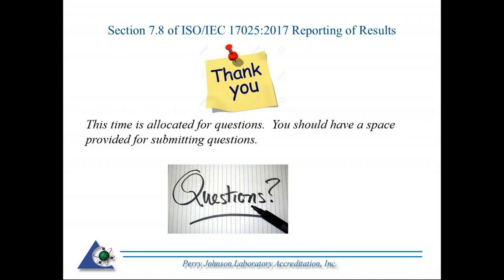Basically, how do you choose plus or minus 2 degrees? Why not 3 for room temperature? Again, this totally depends on the test or calibration that's being done. If you're following a national protocol, such as an ISO standard or ASTM standard, and it specifies those environmental criteria, and you're doing your test or calibration to them, then you need to be following what's in those protocols. If you're picking your own, and what I put there was just a hypothetical situation, 3 may be fine, depending on what test or calibration and what impact the temperature has in play.